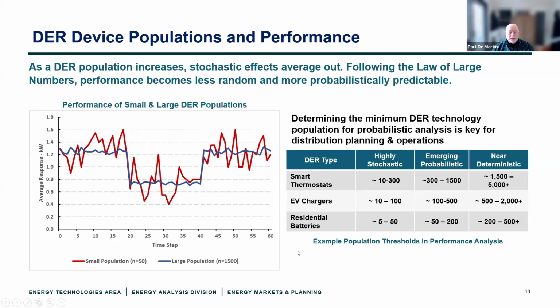To illustrate: when you have a larger population on distribution, say at the substation transformer, you get the blue line on the left in the chart, which is more predictable, dependable performance. But with a small population, say further out on a feeder segment or a lateral, you get a performance characteristic that looks more like the red line.